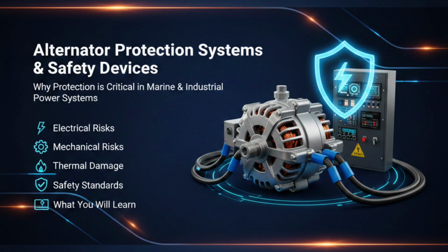Alternators operate under high voltage, high current, mechanical rotation, and thermal stress. Even a small fault, if undetected, can lead to catastrophic damage, blackout situations, or even fire hazards. Protection systems are designed to detect faults instantly and isolate the faulty generator before serious damage occurs. These protections are divided into electrical, mechanical, thermal, and system-based protections.